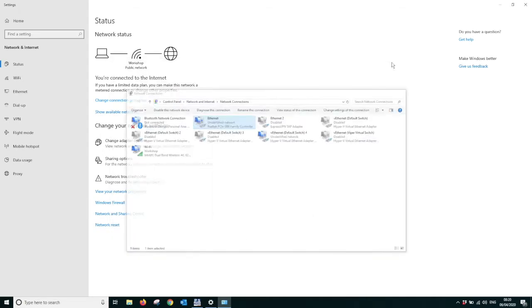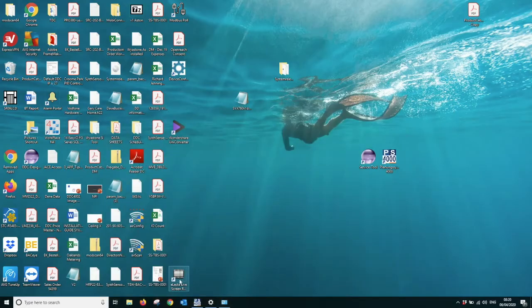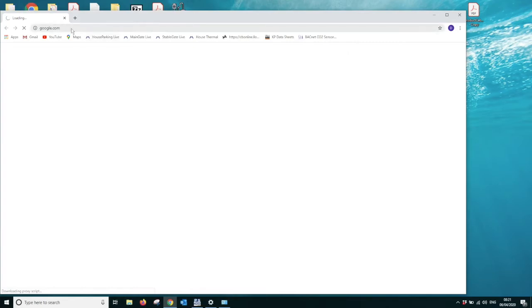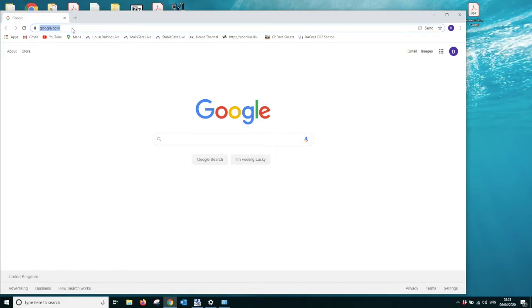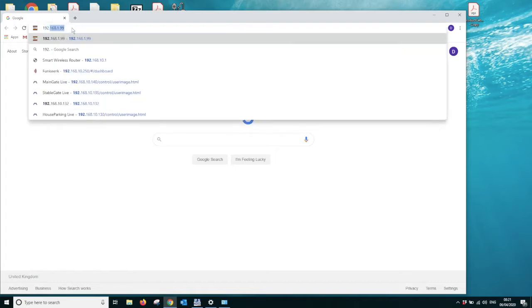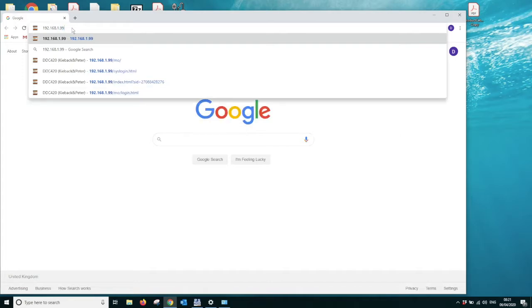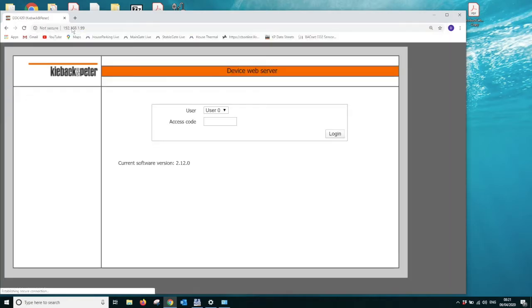and now we can open up a web browser, close down those windows. You can use any web browser. I tend to use Safari or Chrome. I'm going to go for Chrome in this particular case, but I'll show you the other application working at the moment. I'm going to type in the IP address of 192.168.1.99. You can see I've used this before, it's in my history, and I'm going to hit OK, and now I can access the controller.